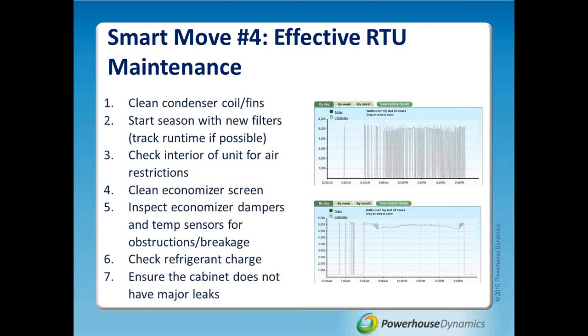The bottom one is the opposite. This is a unit running flat out, and there may be some hot days where this happens, but it's more likely a case of the equipment being dirty or not cleaned well, the condenser coils being dirty, the unit being undersized, or the temperature sensors not being in a good place.